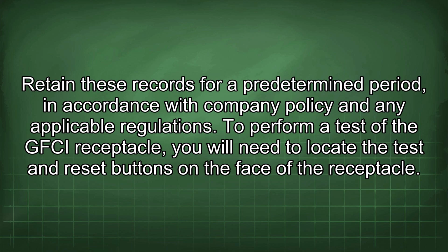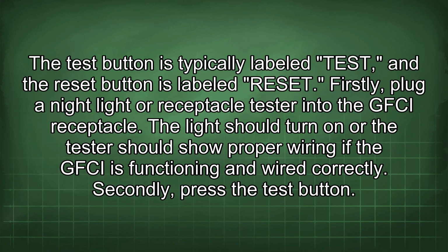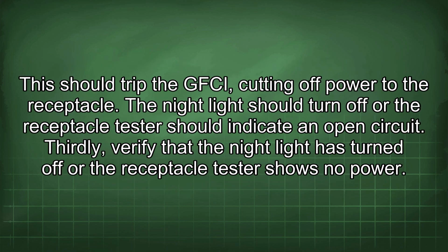To perform a test of the GFCI receptacle, you will need to locate the test and reset buttons on the face of the receptacle. The test button is typically labeled "test," and the reset button is labeled "reset." Firstly, plug a night light or receptacle tester into the GFCI receptacle. The light should turn on or the tester should show proper wiring if the GFCI is functioning and wired correctly. Secondly, press the test button. This should trip the GFCI, cutting off power to the receptacle. The night light should turn off or the receptacle tester should indicate an open circuit.